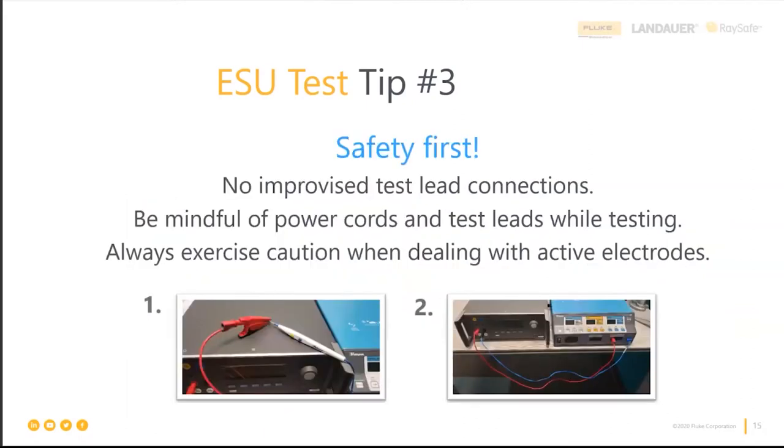Tip number three: safety first. No improvised test lead connections. When using our test equipment, you should have no reason to improvise — we provide everything you need. There's a quiz question on this slide: of the two pictures shown, which is the safe way to do this test — number one or number two? Please type your response into the chat.